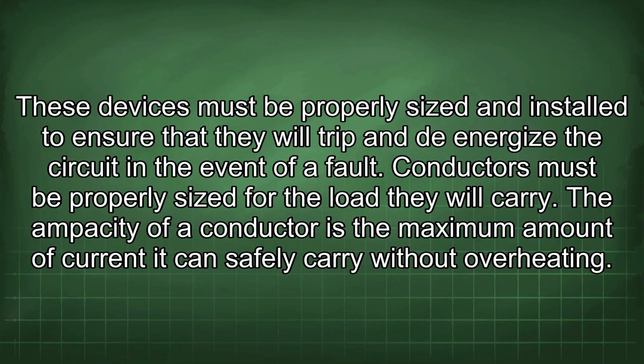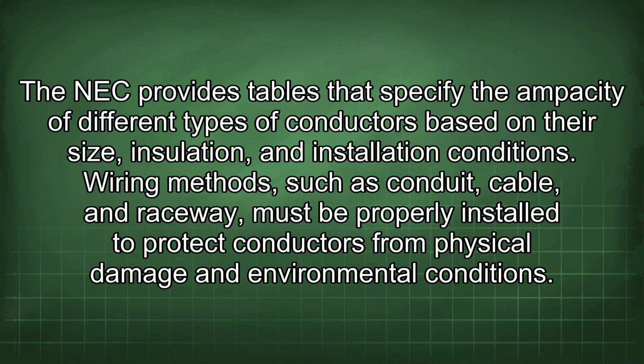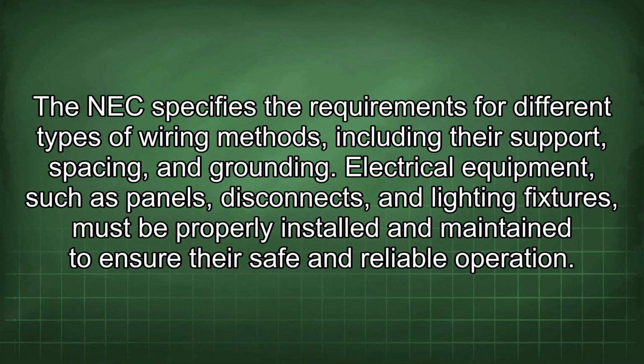Conductors must be properly sized for the load they will carry. The ampacity of a conductor is the maximum amount of current it can safely carry without overheating. The NEC provides tables that specify the ampacity of different types of conductors based on their size, insulation, and installation conditions. Wiring methods such as conduit, cable, and raceway must be properly installed to protect conductors from physical damage and environmental conditions. The NEC specifies the requirements for different types of wiring methods, including their support, spacing, and grounding.